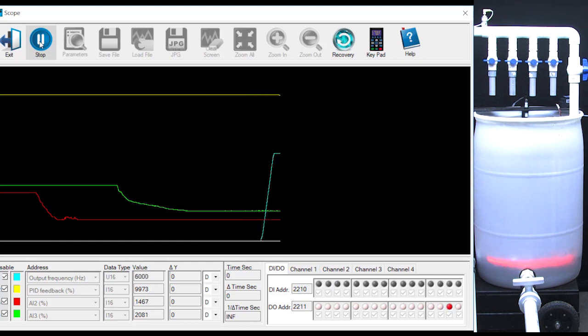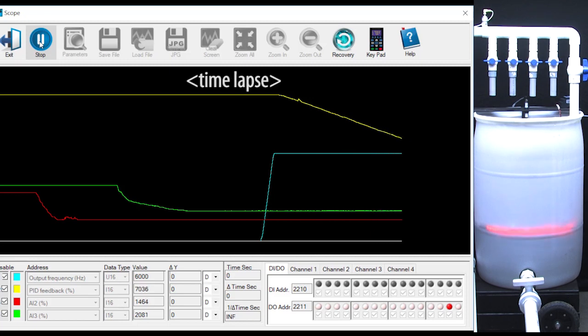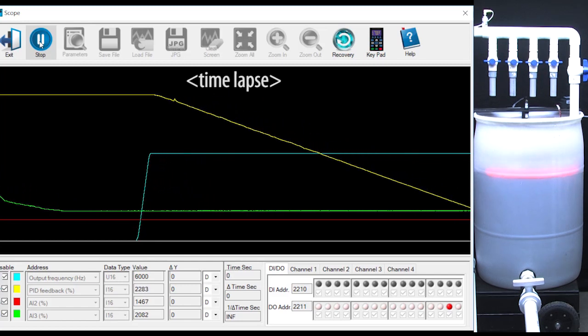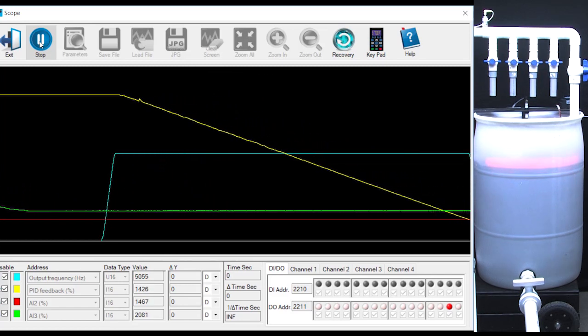PID sees the tank is empty and cranks up the blue drive frequency to try and fill the tank. We see the yellow sensor feedback falling. Remember it falls as the water level rises in a reverse acting system. And when sleep mode sees it cross the red sleep threshold we set, the motor turns off.